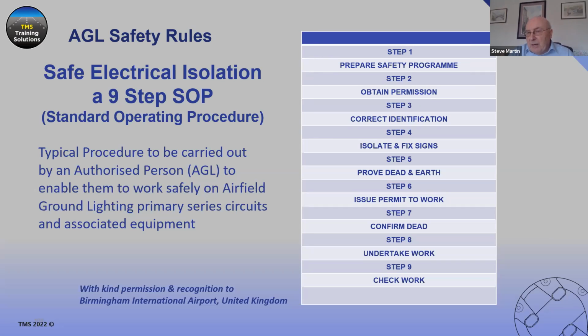Then they prove dead and earth at the output disconnecting device. They'll issue the permit to work or other safety document, confirm dead at the point of work if possible, and undertake the work. When work is complete, they'll check it, agree it's been completed, and the person in charge will return the safety document to the authorized person, who can then cancel that document and start to restore the installation of the circuit.